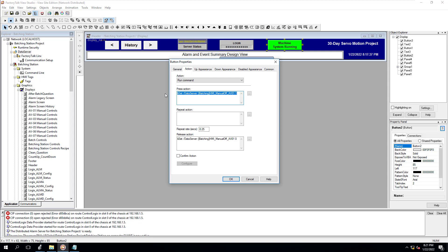When it comes down to it, the difference between controller scope and program scope tags — you need to understand what task you're trying to do. Are you trying to keep everything local, or do you want global access and the flexibility to utilize tags throughout the whole PLC code? If so, go controller scope. If you're trying to keep it local, use program scope tags — but keep in mind you'll have a harder time setting up communications with the HMI or OPC server. This applies to both Studio 5000 and RSLogix 5000.